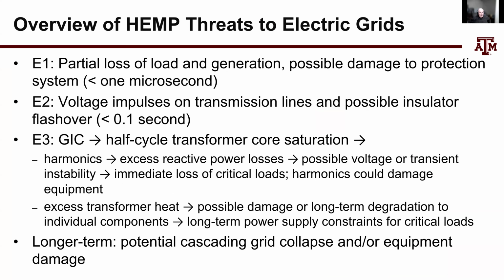In terms of the threats these cause to the grid, E1 could cause partial loss of load and generation, and potentially damage to the protection system. E2 is similar to lightning; it might cause some insulation flashover.